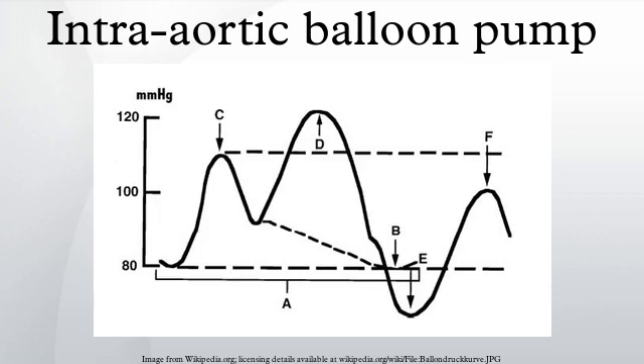It consists of a cylindrical polyethylene balloon that sits in the aorta, approximately 2 cm from the left subclavian artery and counterpulsates. That is, it actively deflates in systole, increasing forward blood flow by reducing afterload through a vacuum effect.